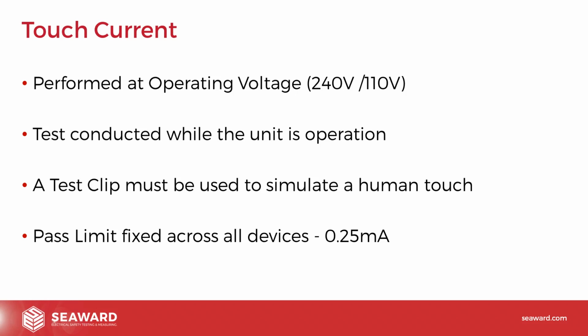Now what we do when it flows through that test clip is we also divert that current through what we call a body model. For those of you that have been on any of our previous webinars, we talk about the resistance of the human body. We have a rough resistance of somewhere in the region of 1500 to 2000 ohms. So essentially what we do is we divert this current through the body model, which is essentially a 2000 ohm resistor, and this gives us a realistic value for what current we would be exposed to if there's an issue with the product under test.